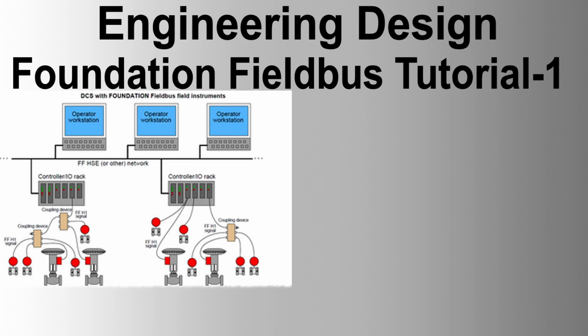Maintenance phase. Fieldbus allows for the reporting of self-diagnostics, calibration, and environmental conditions of field instruments without disturbing the plant control. Since it uses intelligent instruments, your stock for spare or replacement instruments can be dramatically reduced. Software packages for asset management are useful to minimize maintenance costs.